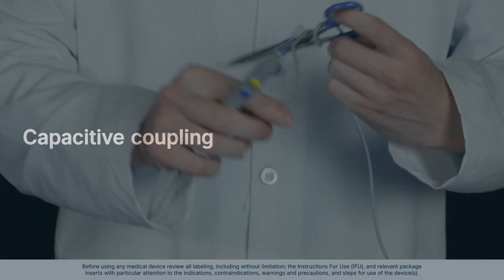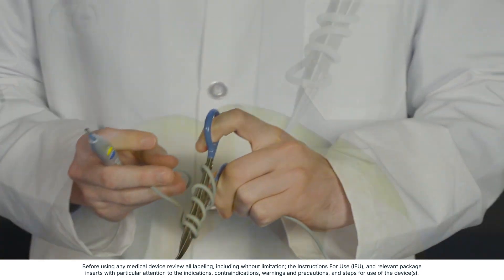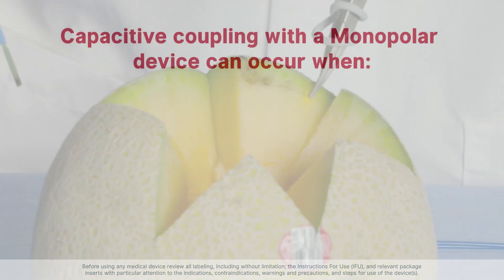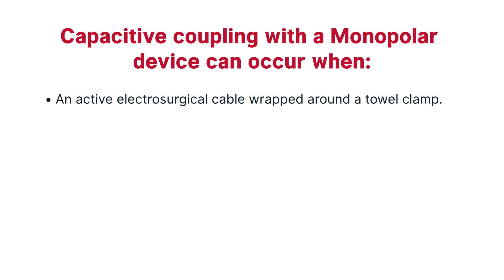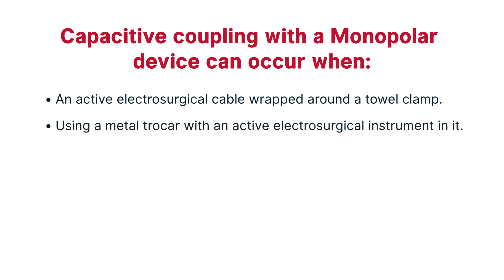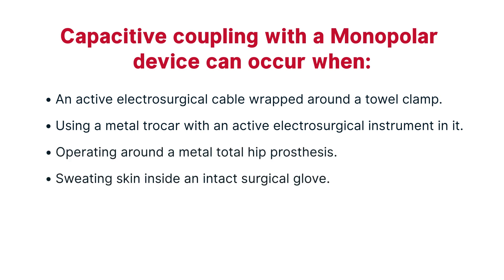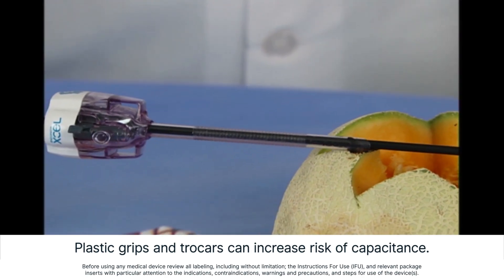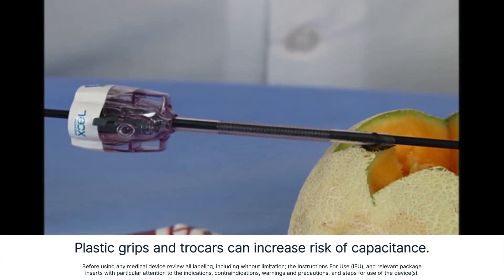Capacitive coupling. When an insulator separates two conductors, the insulator serves as a capacitor and creates an electrostatic field. Thus, a current in one conductor can induce a current in the other. Capacitive coupling with a monopolar device can occur under any one of the following circumstances: an active electrosurgical cable wrapped around a towel clamp; using a metal trocar with an active electrosurgical instrument in it; operating around a metal total hip prosthesis; sweating skin inside an intact surgical glove; a metal cannula around an active electrosurgical instrument. The smaller the cannula, the greater the risk for capacitance. The risk increases when a metal cannula has a plastic grip around it.